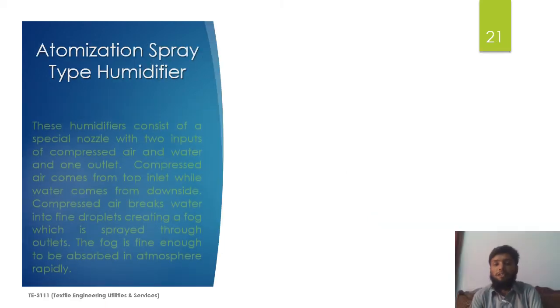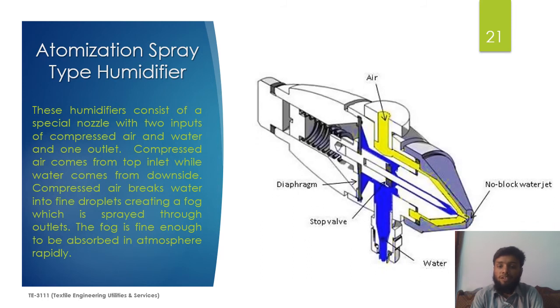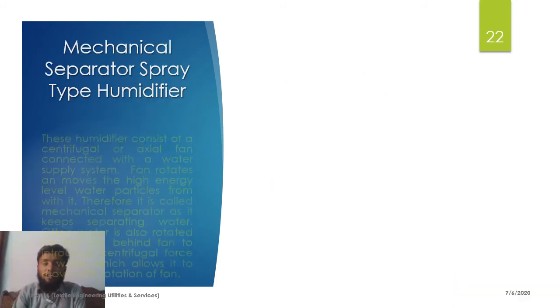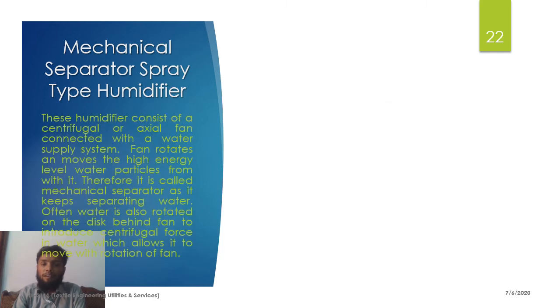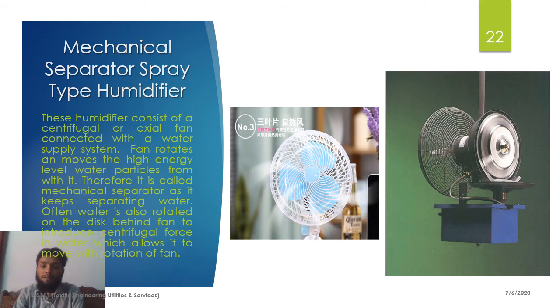The first type is the atomization spray type humidifier, which uses a combination of compressed air and water to produce a fine fog of water droplets that maintains the humidity of the environment. The second type is the mechanical separator spray type humidifier, which uses centrifugal or axial fans and a rotating disc at the back that throws water in the form of droplets to maintain the humidity level.